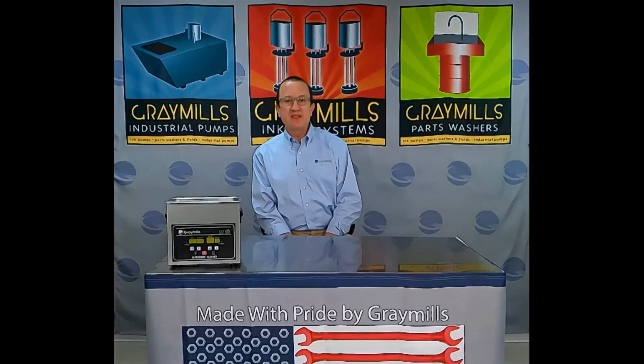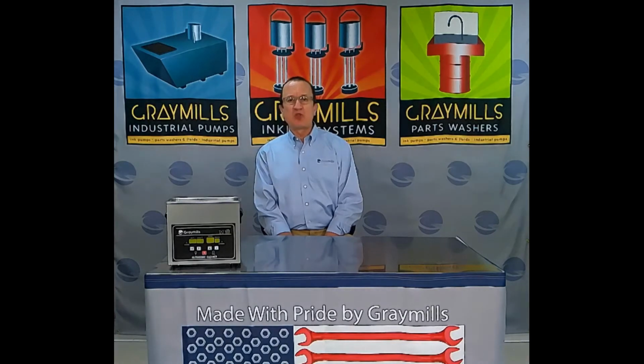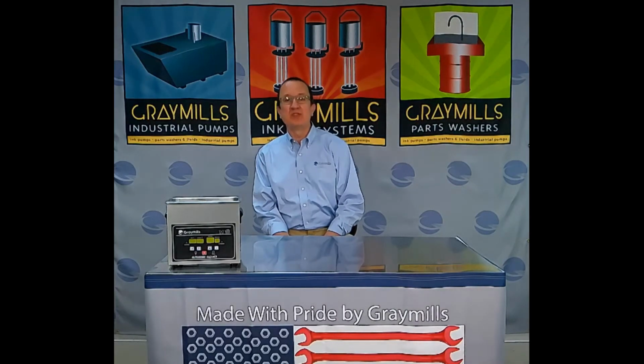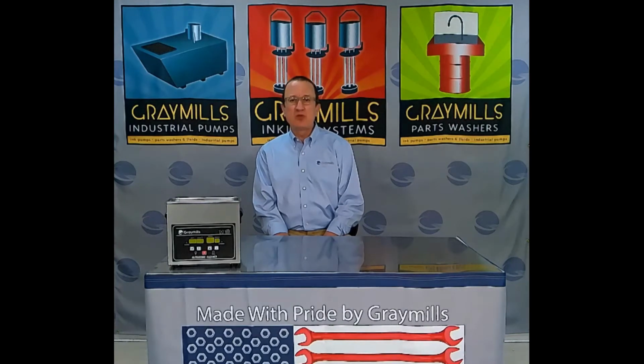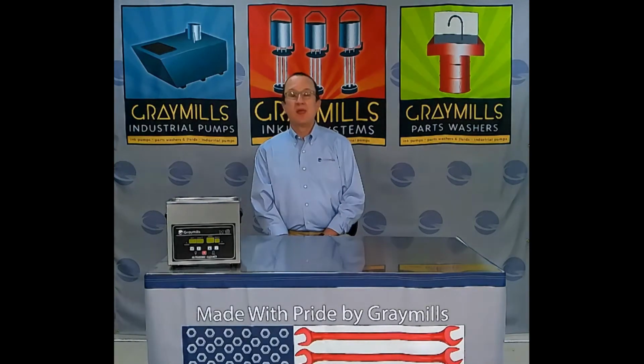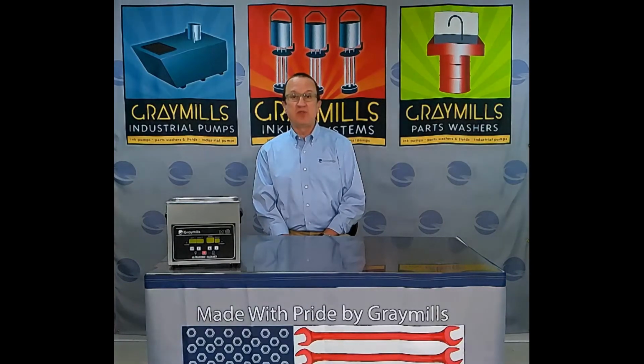One thing you'll hear about when you spec ultrasonic parts washers is the frequency, which describes how fast these waves happen. At the low end, about 25 kilohertz, you get washers that are very good for robust, strong cleaning. At the high end, around 68 kilohertz, you get washers good for precision cleaning that are a little gentler. Some split the difference around 40 kilohertz, giving you the best of both worlds.